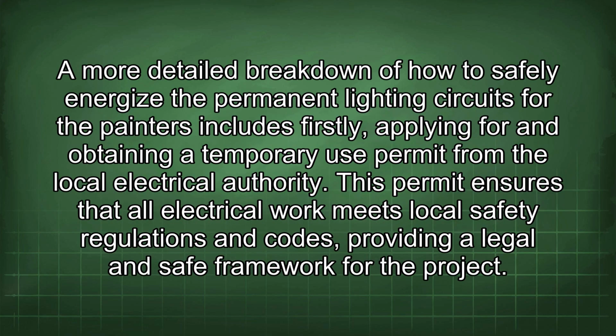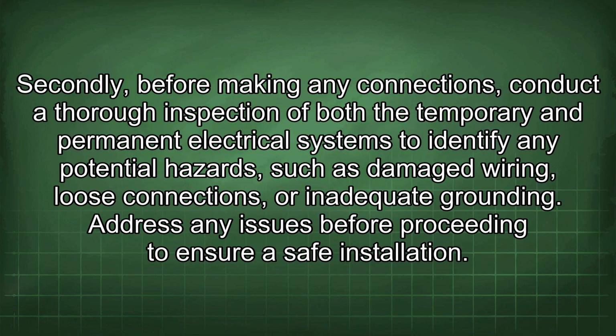A more detailed breakdown of how to safely energize the permanent lighting circuits for the painters includes, firstly, applying for and obtaining a temporary use permit from the local electrical authority. This permit ensures that all electrical work meets local safety regulations and codes, providing a legal and safe framework for the project. Secondly, before making any connections, conduct a thorough inspection of both the temporary and permanent electrical systems to identify any potential hazards, such as damaged wiring, loose connections, or inadequate grounding. Address any issues before proceeding to ensure a safe installation.